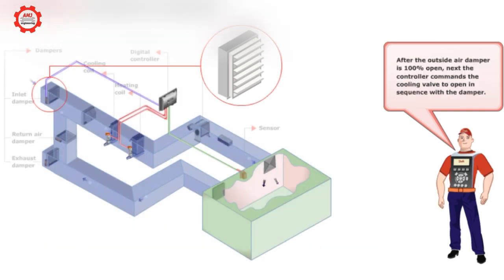After the outside air damper is 100% open, next the controller commands the cooling valve to open in sequence with the damper.